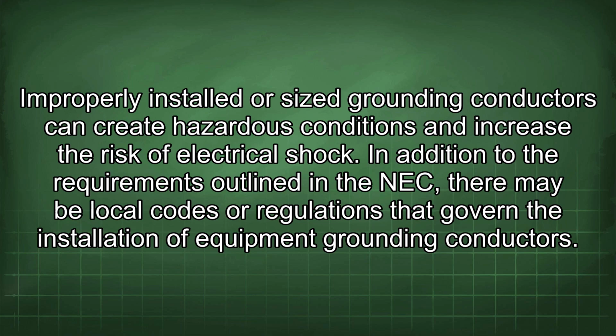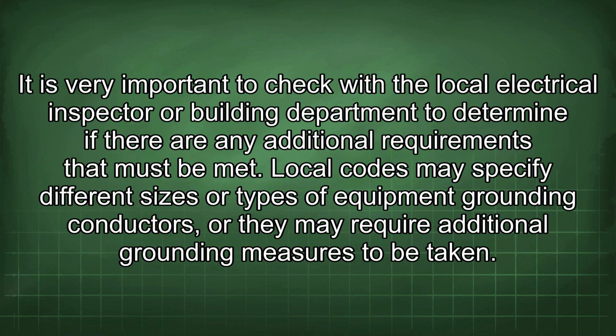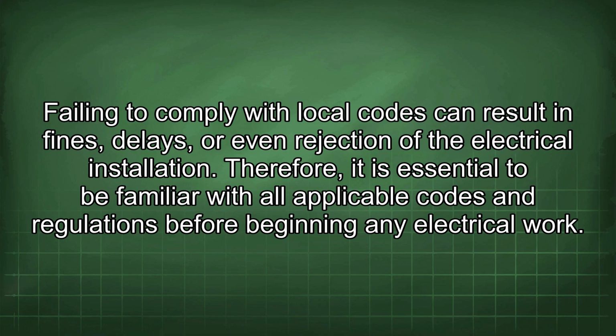In addition to the requirements outlined in the NEC, there may be local codes or regulations that govern the installation of equipment grounding conductors. It is very important to check with the local electrical inspector or building department to determine if there are any additional requirements that must be met. Local codes may specify different sizes or types of equipment grounding conductors, or they may require additional grounding measures to be taken. Failing to comply with local codes can result in fines, delays, or even rejection of the electrical installation. Therefore, it is essential to be familiar with all applicable codes and regulations before beginning any electrical work.